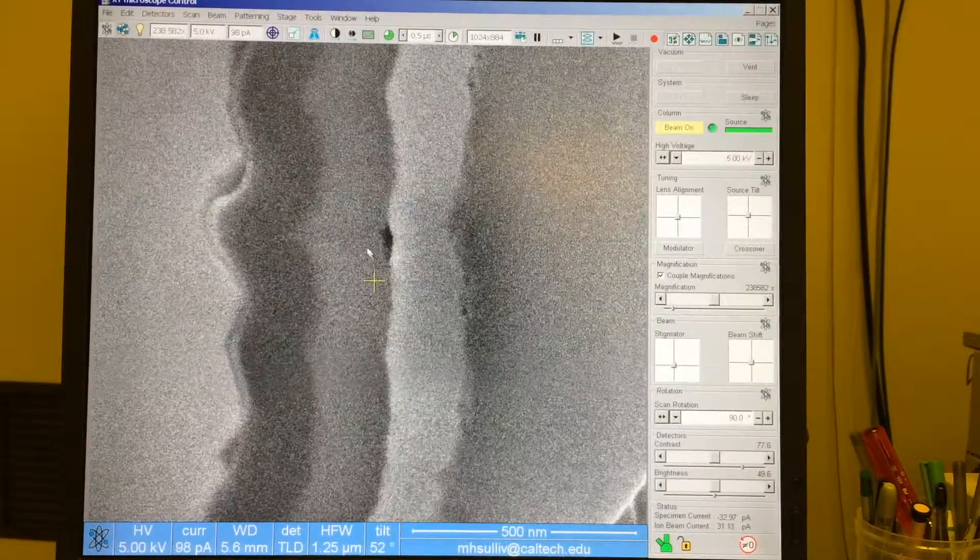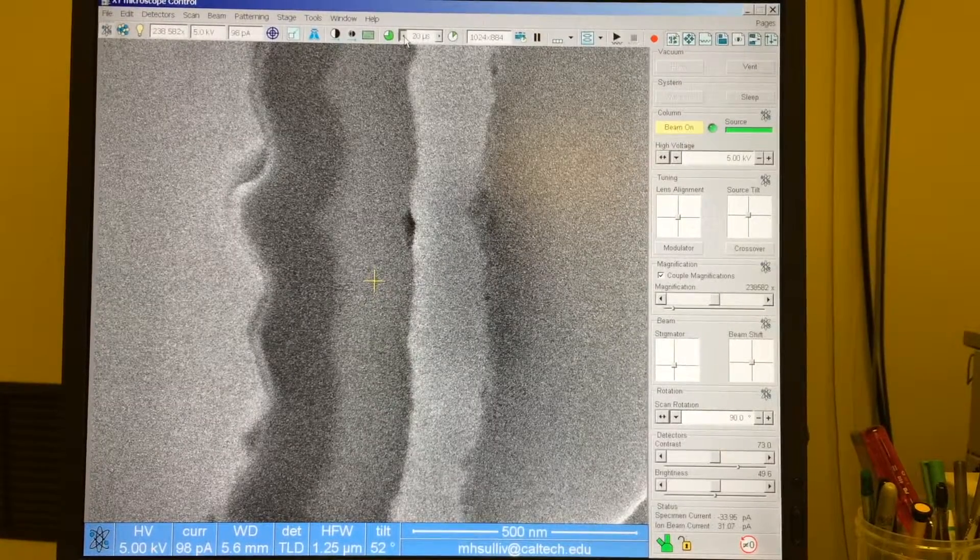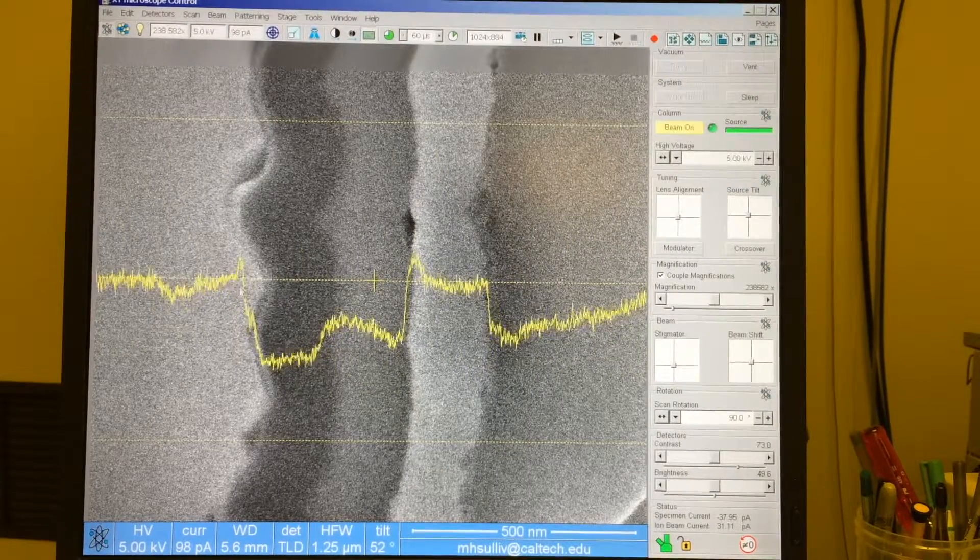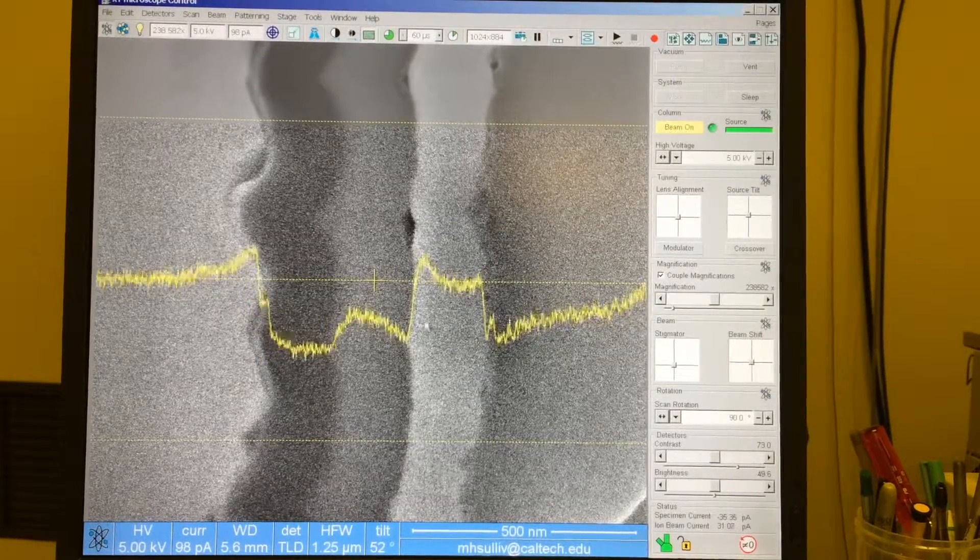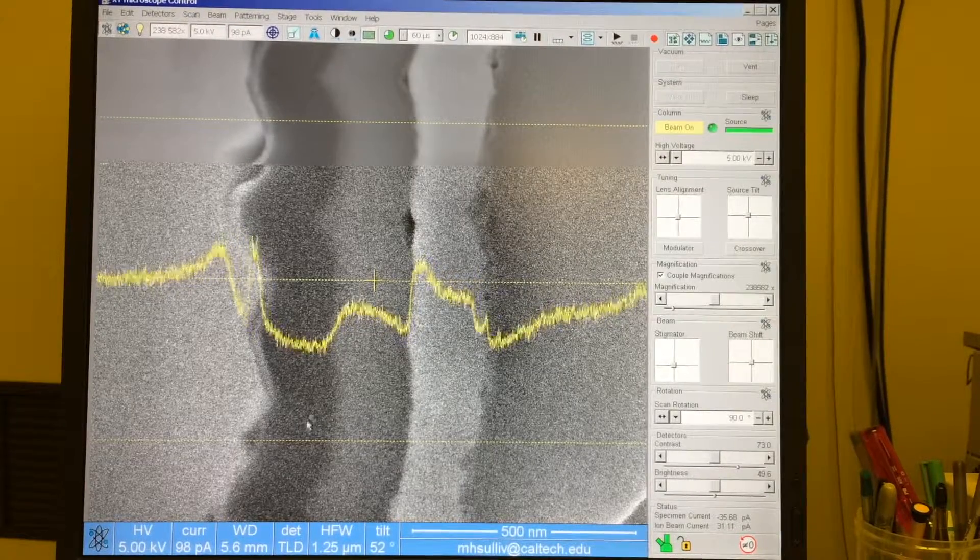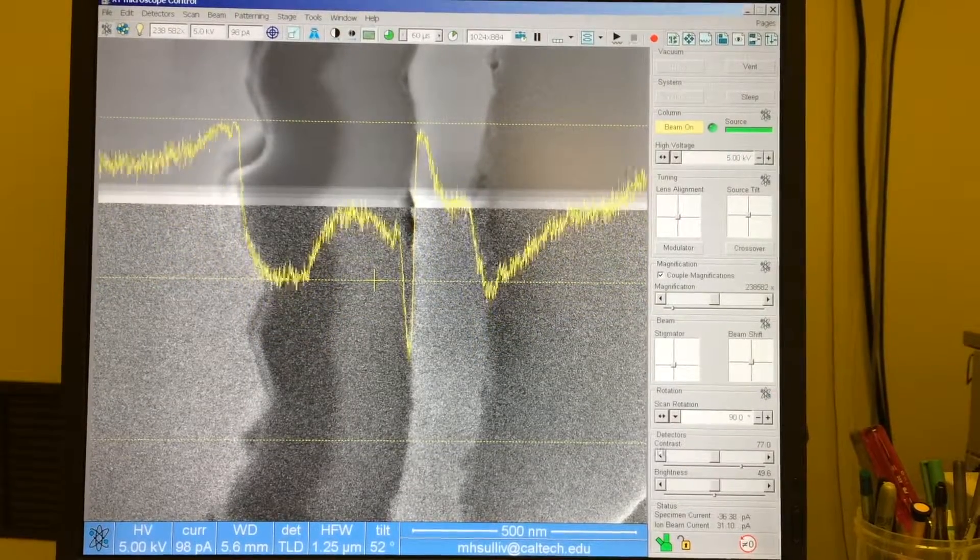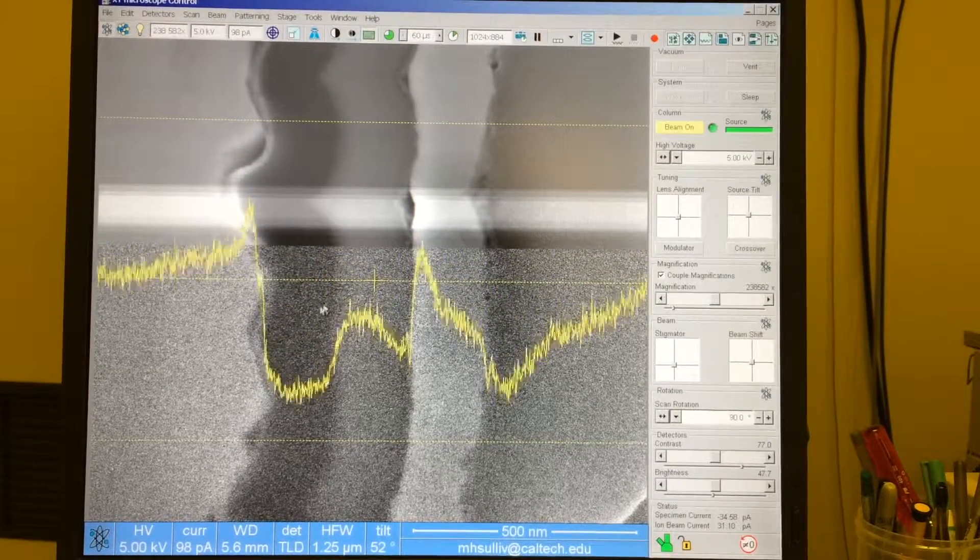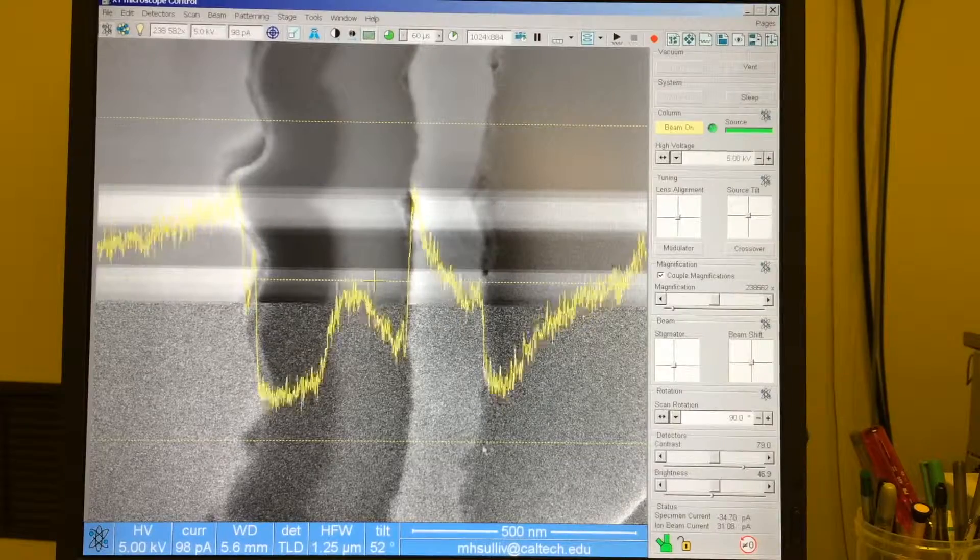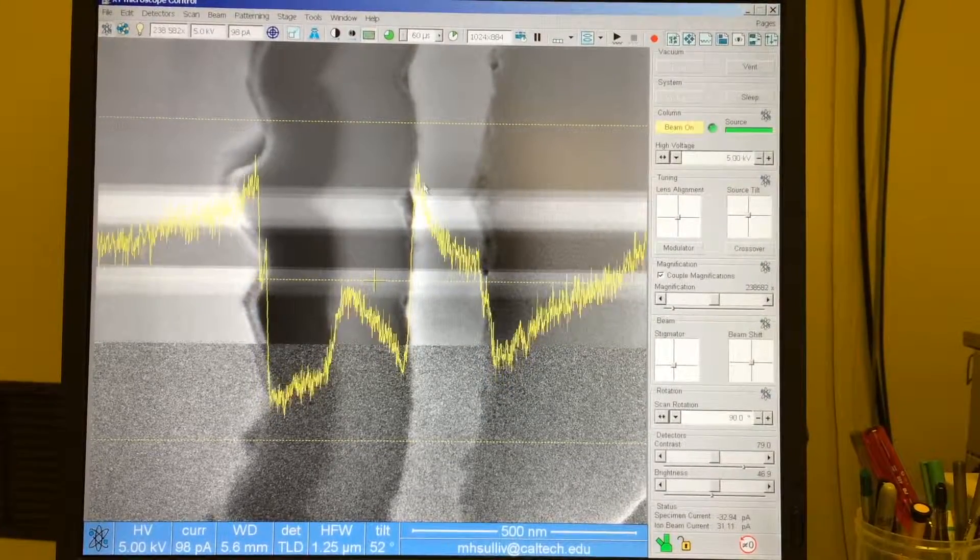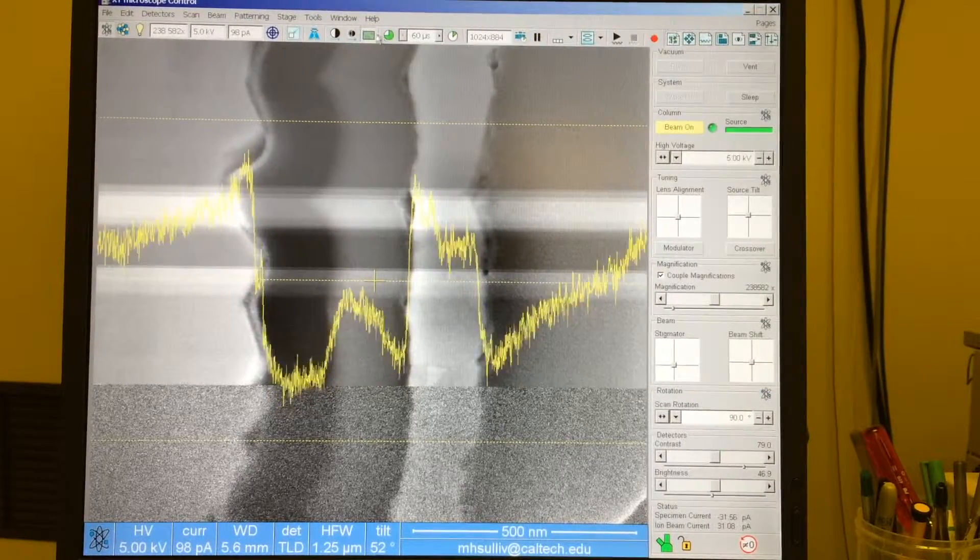And you turn off that window. Now when I scan at my 60 microsecond dwell time and turn on the video scope, I have essentially a static video scope where I can see all the different gray levels of my layers at the same time. So I want to maximize the amplitude of this so that my brightest pixels are somewhere near the top and my darkest pixels are somewhere near the bottom. To do that, I'll increase the contrast that increases the amplitude of my graph, and I'll lower the brightness to lower the entire graph. Maybe repeat this a little bit. So now I have some dark pixels near the bottom but not perfectly saturated dark, and some white pixels near the top but not saturated white. So that gives me a nice video scope.